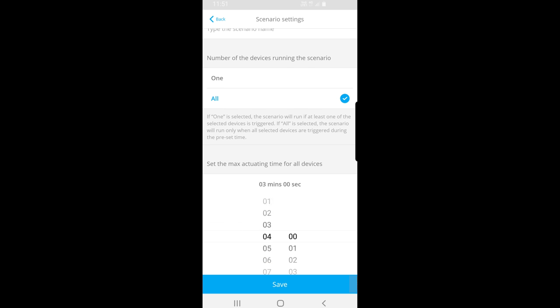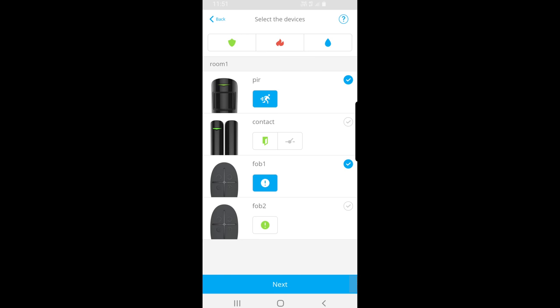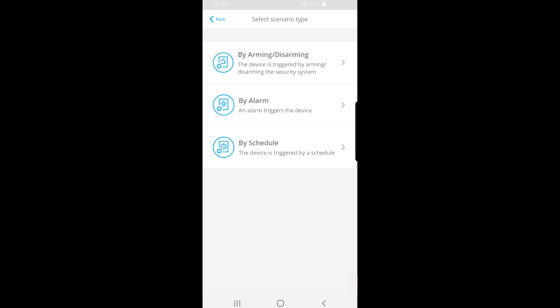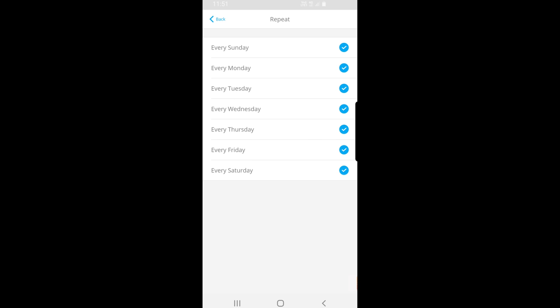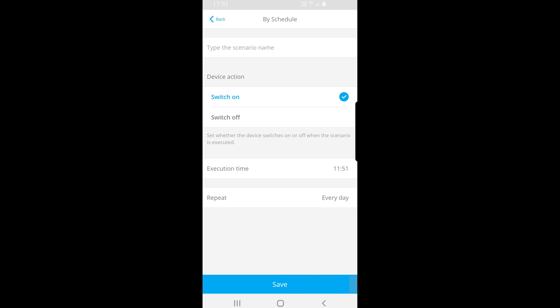Or you can select the 'All' option and set a time period within which all chosen detectors must operate to then trigger the relay contact — kind of like a double knock, where if one then another triggers within a set time period, the relay contact will operate. There's also a 'Schedule' option where you can set a specific time of day for the alarm contact to trigger and choose different days for different times.